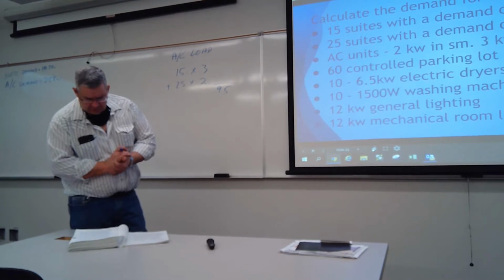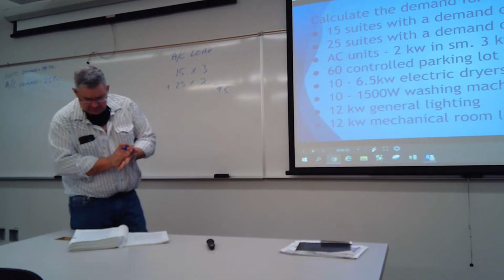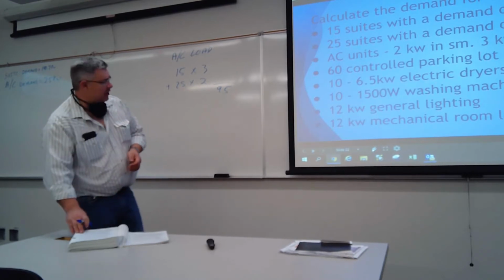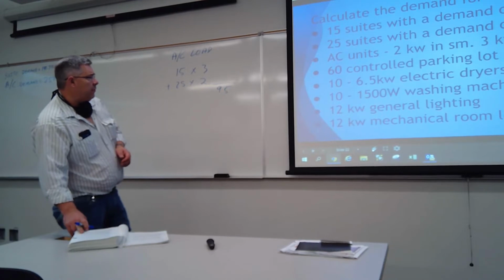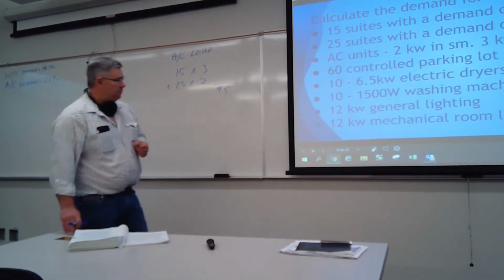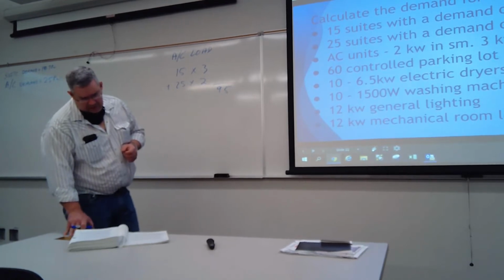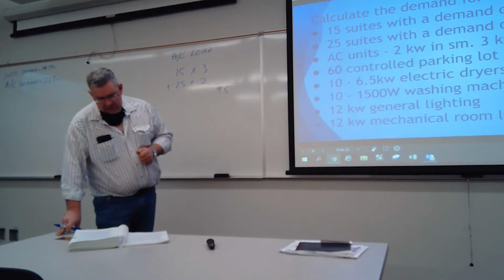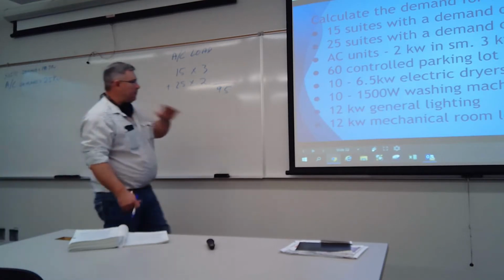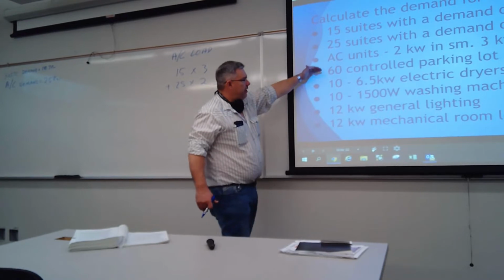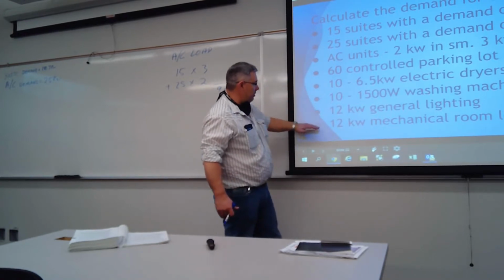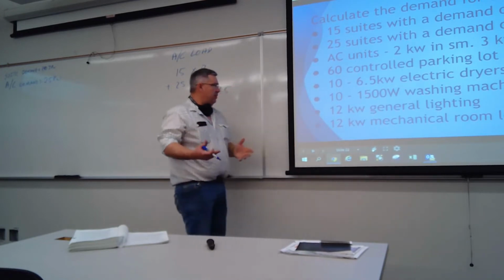Now we're on to D, any electrical vehicle supply equipment loads not located in the dwelling units shall be added with a demand factor as specified in table 38. We don't have electrical vehicle chargers, we have controlled parking lot plugs, so D doesn't apply. In addition, any lighting, heating, and power loads not located in the dwelling unit shall be added with a demand factor of 75%. So basically everything we haven't counted up, which is our parking lot plugs, dryers, wash machines, lighting, and the mechanical room load. We take all that, add it all together, and apply a demand factor of 75%.